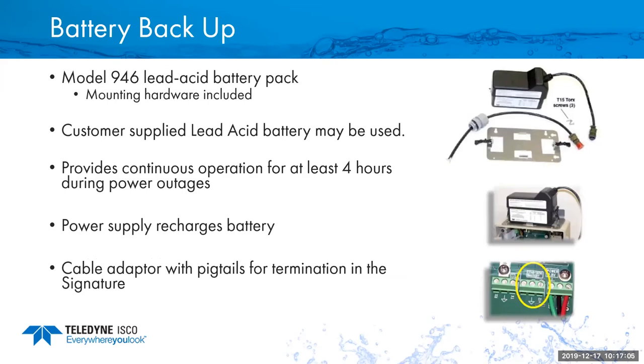The battery backup uses one of our 946 lead acid batteries, and it's used to get us about 4 hours of additional power usage and let the meter run for that time in a power outage of AC power. And then as the power would come back on, it would recharge the battery. So if another event occurred, you'd know the battery would be charged up without having to pull it out of the field. There is a two-pin Amphenol connection, so you're just able to wire that directly into the signature and then connect the battery up to that two-pin Amphenol on the outside. So it installs fairly easily in the field as necessary.